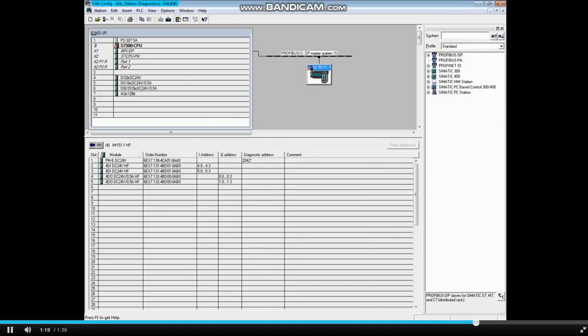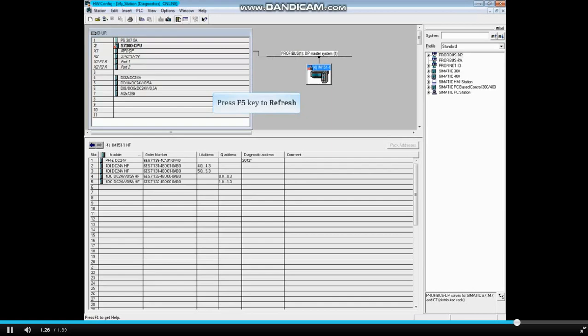The wire was seated properly, and the terminal retightened, which fixed the problem. To refresh the online hardware configuration, press the F5 key. The station is now up and running, and that concludes this video.